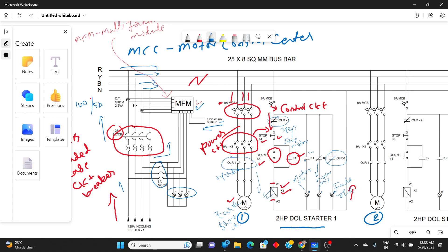When the OLR operates, the normally closed contact opens, stopping the motor. The coil is de-energized, so the normally open auxiliary contact returns to its normal open position. Once the overload relay operates, the motor turns off, K1 is turned off, and the circuit returns to its original position showing that the motor is off and overload has occurred. The same circuit is then duplicated for the second motor.